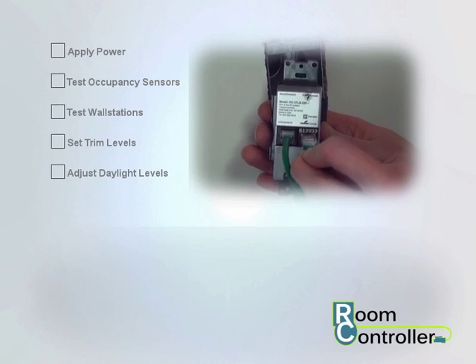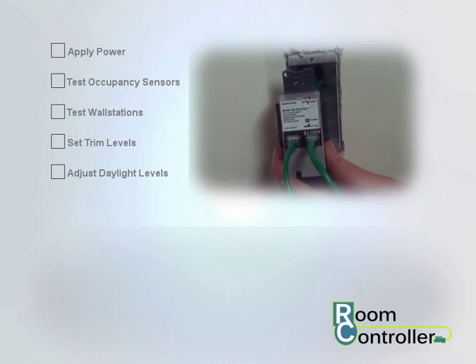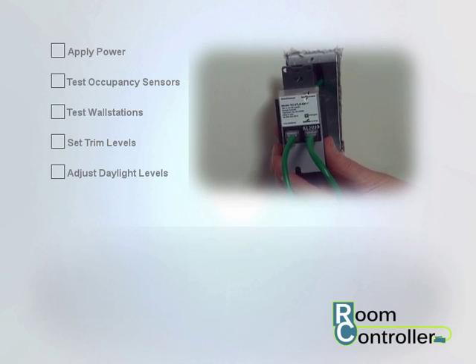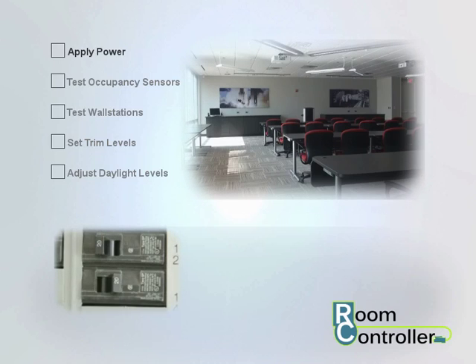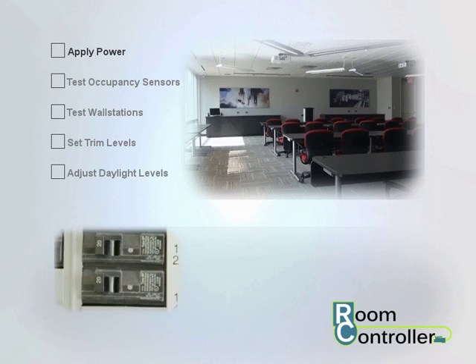Once the room controller components are installed, you are ready to verify the room controller operation. Apply power to the room controller and verify that the lighting loads turn on full bright for 3 seconds before they begin normal operation.